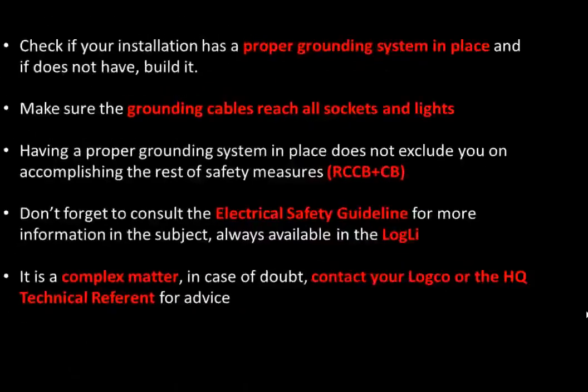So remember, in order to have a proper grounding system, check if your installation has a proper grounding system in place. If it does not have, build it. Make sure the grounding cables reach all electrical sockets and lights. Having a proper grounding system in place does not exclude you from encompassing the rest of the safety measures, RCCB and CB. Don't forget to consult the electrical safety guideline for more information about the subject. It is a complex matter.